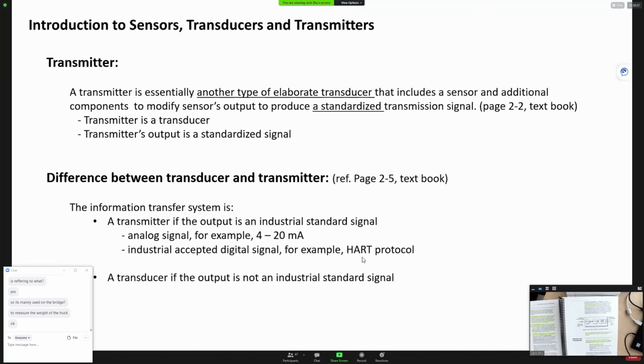All those are digital communication. The new ones now even use a normal network protocol like TCP/IP. So the difference between a transducer and a transmitter is that all transmitters belong in the transducer category. But to be qualified to be called a transmitter, they have to have a standardized output signal. If they don't output a standardized signal, you can only call them a transducer. You cannot call them a transmitter.